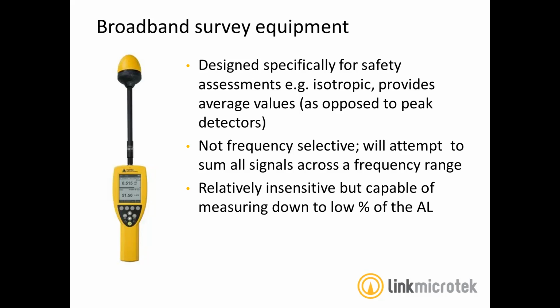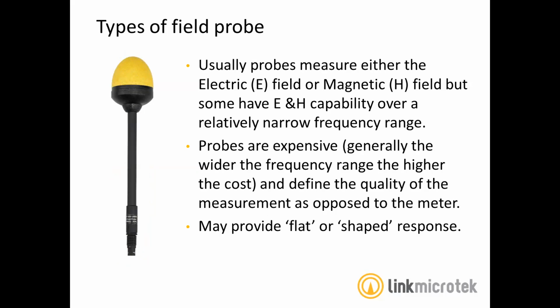The important thing with this is the selection of the probe, making sure that the probe you're using is capable of covering the action level and beyond. The probes for these meters are usually electric field or magnetic field, but some have an E plus H capability over a relatively narrow frequency range, such as the NARDA industrial meters, which are specifically designed for 27 megahertz heat sealers, and they measure both.